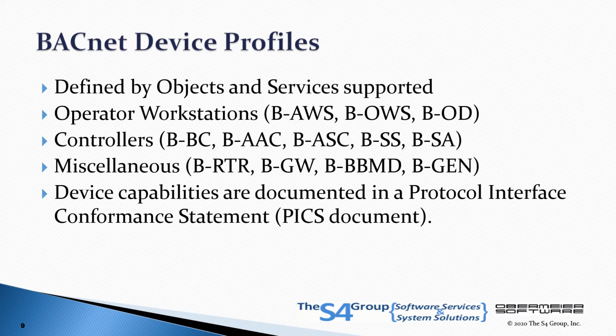BACnet device profiles provide a way of defining the core functionality provided by a device. The details are documented in the Protocol Interface Conformance Statement, or PICS, document provided by the manufacturer for each device.